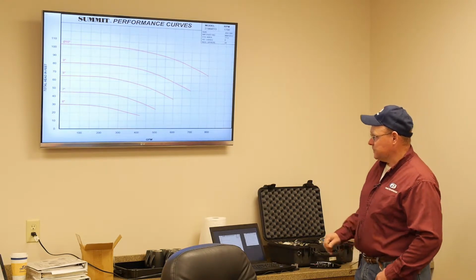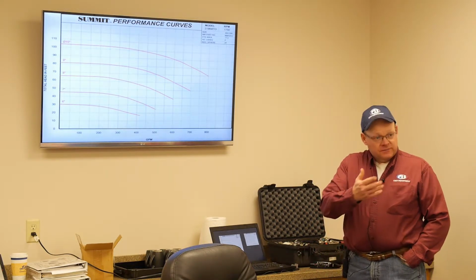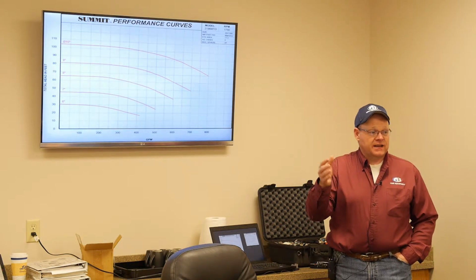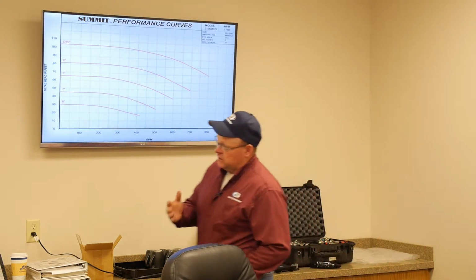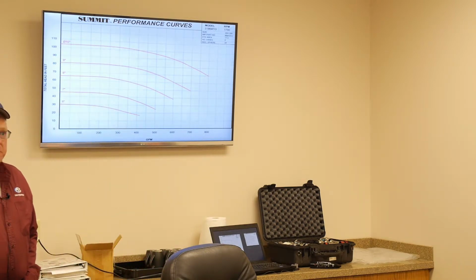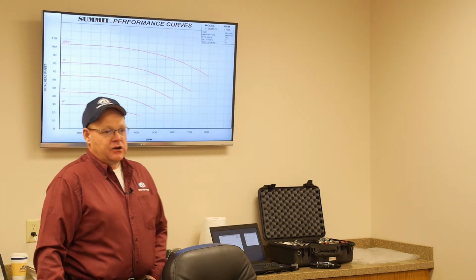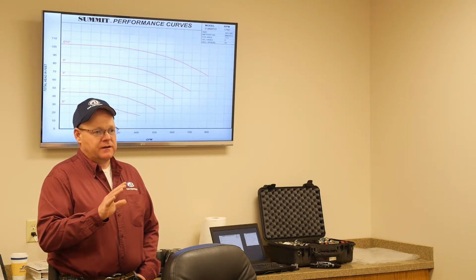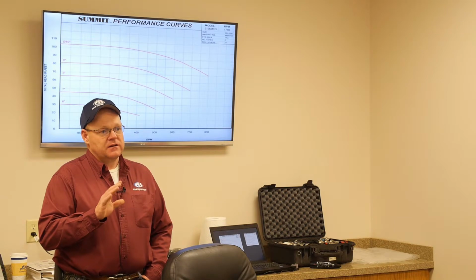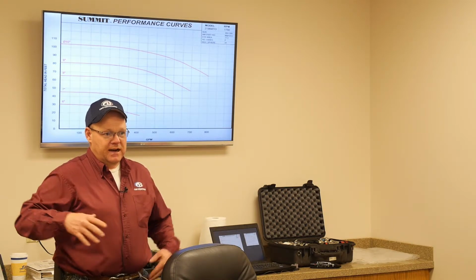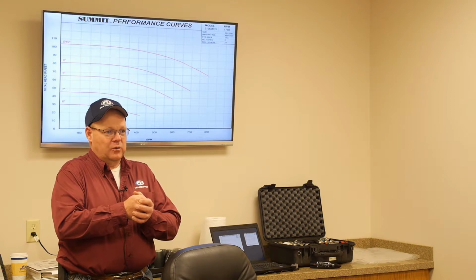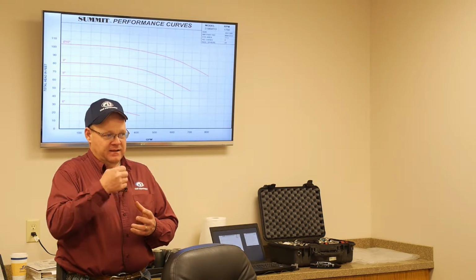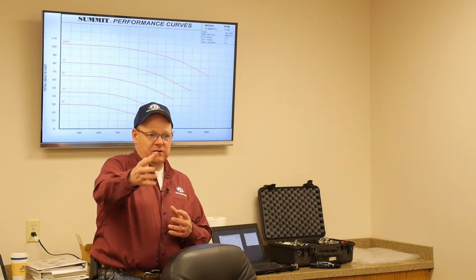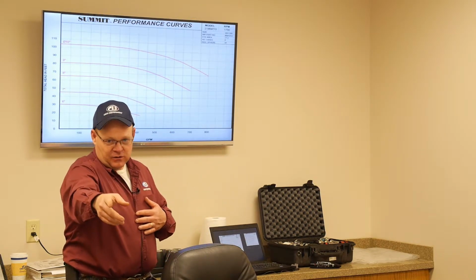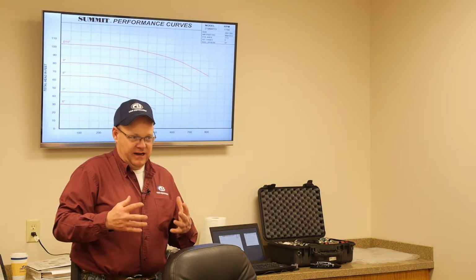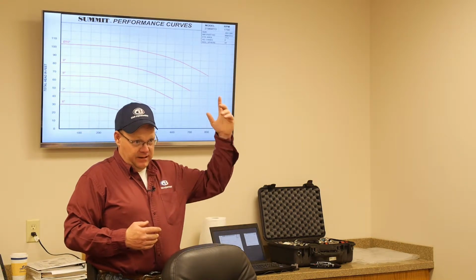It'll just be flat. What's the purpose of two different sizes? Flow, performance, head, all those things are going to be affected, and right over here, if you want to look at it. 4x4 wouldn't do the same thing as a 3x4? Nope. All of your ANSI stuff and most of all of your centrifugals are going to have a smaller discharge than they do suction. Because why? We're taking in more volume and squeezing it through a little bitty hole. So in turn we're increasing the pressure. That's how most centrifugals work. Now on some of your 3x3s, 4x4s, your Gorman Rupp stuff, we're not really trying to create a lot of pressure. We're just trying to get some stuff to go through one hole and out the other.